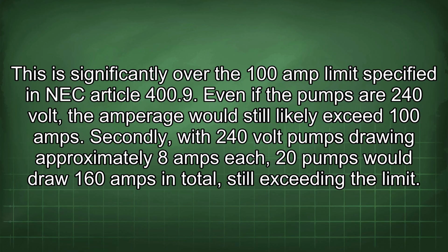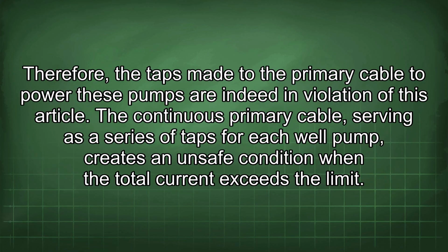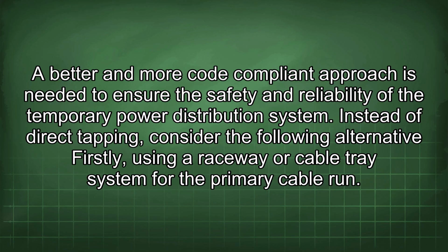Even if the pumps are 240 volt, the amperage would still likely exceed 100 amps. Secondly, with 240 volt pumps drawing approximately 8 amps each, 20 pumps would draw 160 amps in total, still exceeding the limit. Therefore, the taps made to the primary cable to power these pumps are indeed in violation of this article. The continuous primary cable, serving as a series of taps for each well pump, creates an unsafe condition when the total current exceeds the limit. A better and more code-compliant approach is needed to ensure the safety and reliability of the temporary power distribution system.